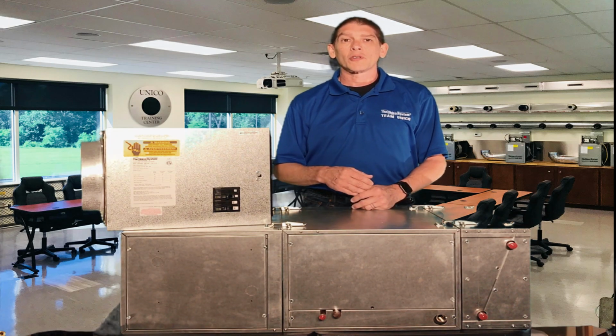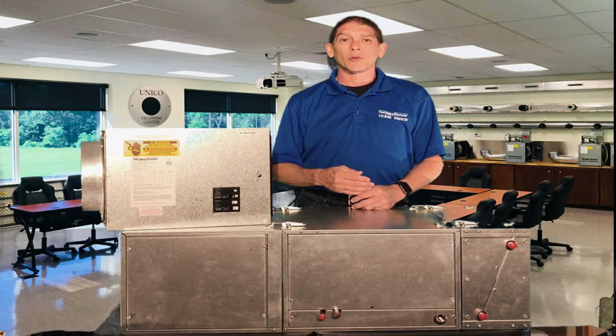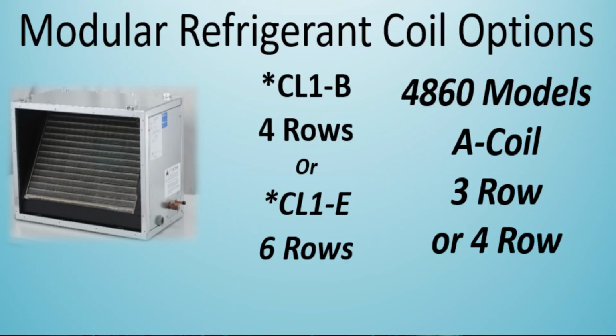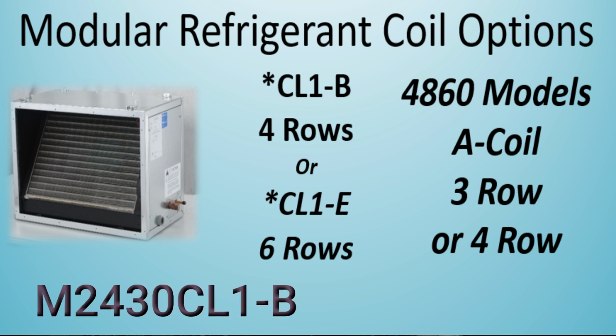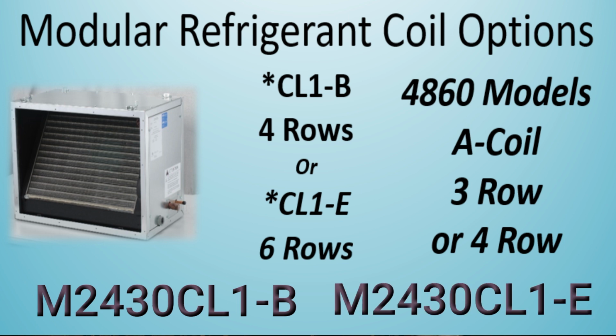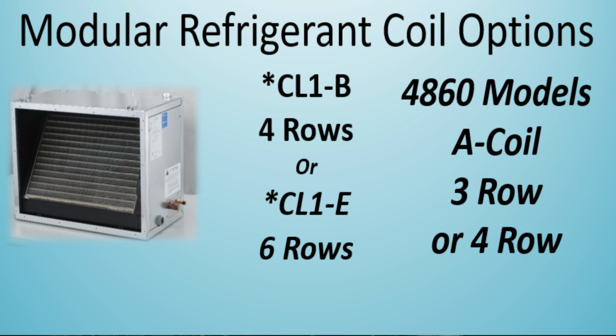All of our refrigerant coils are air conditioning and heat pump compatible. We have two different thicknesses to accommodate most heat pumps. The model numbers will end with a B or an E. For example, M2430 CL1B or an M2430 CL1E. Our E coils have two extra rows for expansion when in heating mode. Most of the time, this is a coil you will use with a heat pump. But if you're not sure, give us a call or shoot us an email and we'll match the coil with the model of the heat pump you are installing.